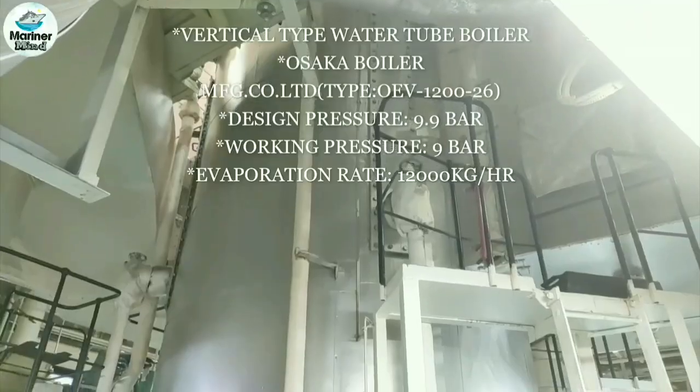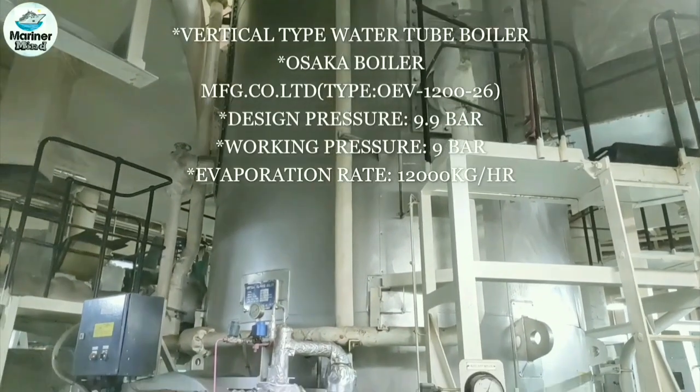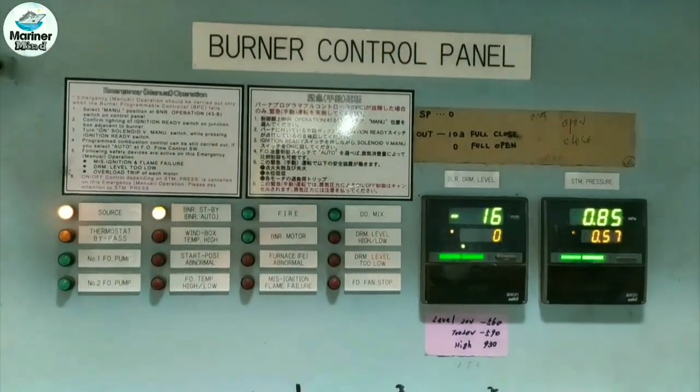This is a vertical type water tube boiler made by Osaka Boiler Manufacturing. Design pressure is 9.9 bar, working pressure is 9 bar, and evaporation rate is 12,000 kg per hour. Before starting work, ensure that the boiler has been changed over to diesel oil.